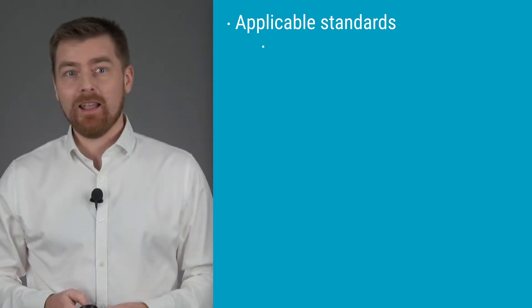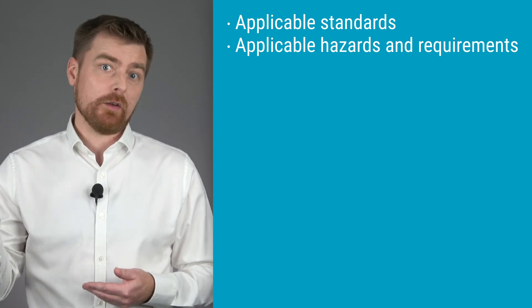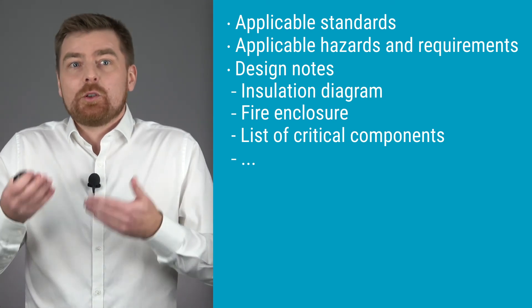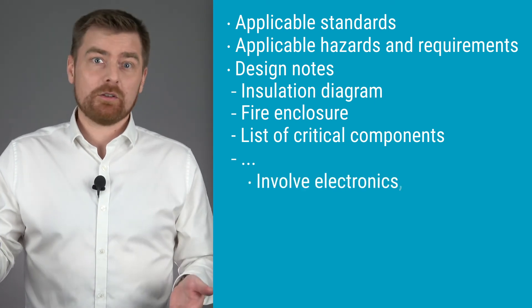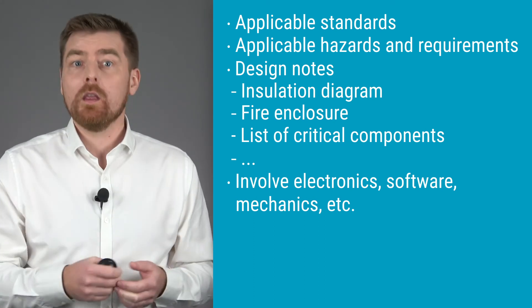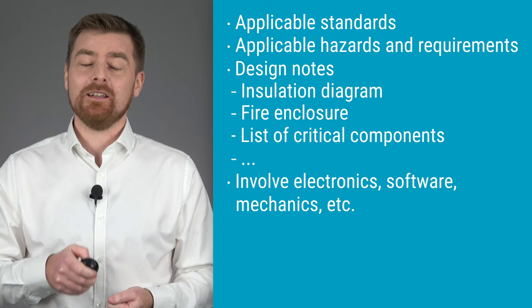To avoid costly delays, I recommend that you identify the few relevant requirements early during the design phase and decide how the design is going to meet these requirements. The key to proactive safety by design is to start early, and based on the intended purpose and technologies, identify which standards are applicable to your device, and which of the hazards and requirements apply. Then document in design notes how the product is designed to be safe. It is critical to do this as a cross-functional team exercise, because it is the combination of electronic, mechanic and software solutions that must meet the requirements. Risk management should be a team effort and safety is a system property.